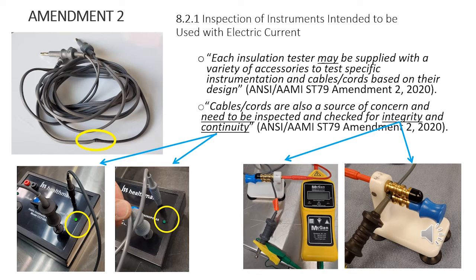In regards to continuity, as you see in the pictures on the left, this is going to mimic the generator unit. So what you would do is plug in the proximal and the distal end of the monopolar cable, and then you would see a light go on. When the light goes on, that means there's a connection, but you also have to wiggle and play with the proximal and distal end as well as the whole cable itself. And what you're looking for is any flickering.